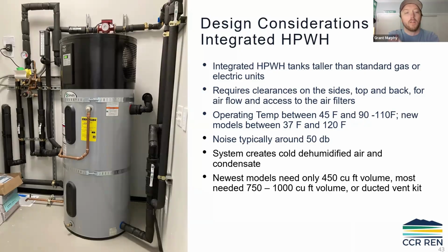Yeah, totally. So this has been the biggest pain of the previous code cycle and the heat pump water heater craze right now. When these things came on the market, they were fairly new. They had existed, but the amount of them being purchased and installed was dramatic, and code was forcing people into this situation. The initial ones that came out, you can see that last bullet, said 750 to 1,000 cubic feet of volume. That was the original spec on a lot of those units.